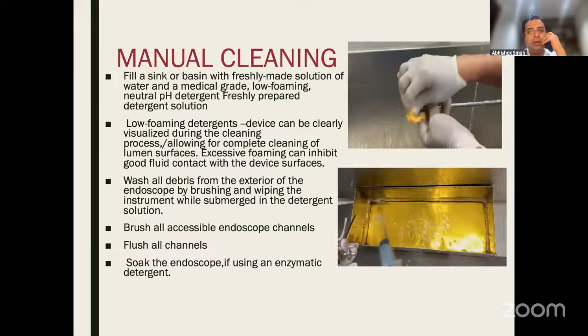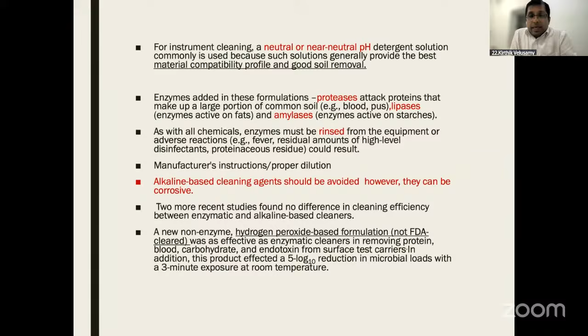Little bit about what kind of solutions we use. There are a variety of solutions available in the market. Ideally, it should be neutral or near neutral pH because it is compatible with the material and good dirt removal will be useful. Enzymatic solutions are preferable because they contain protease, lipase, and amylase. Each has its own function. As soon as soaking is done, it should be rinsed to avoid any disinfectants going into the patient or going into the sterile department. Alkaline-based cleaning agents should be avoided as they can be corrosive.